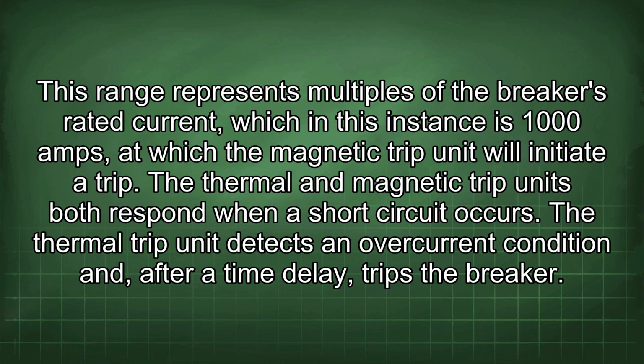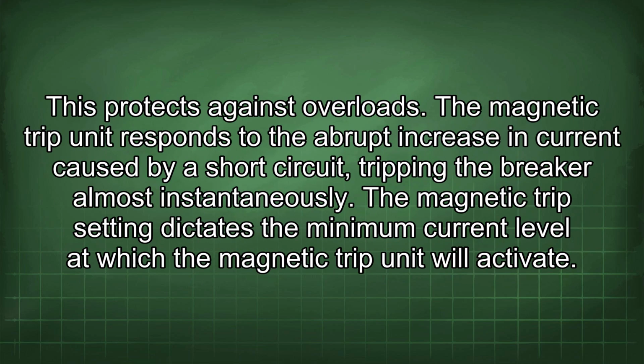The thermal and magnetic trip units both respond when a short circuit occurs. The thermal trip unit detects an overcurrent condition and, after a time delay, trips the breaker. This protects against overloads. The magnetic trip unit responds to the abrupt increase in current caused by a short circuit, tripping the breaker almost instantaneously. The magnetic trip setting dictates the minimum current level at which the magnetic trip unit will activate.